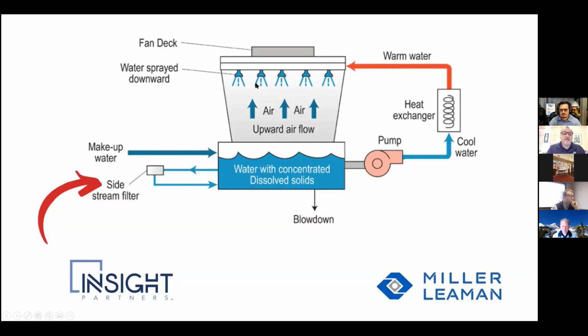We're going to be talking about side stream filtration, where we're pulling it out of the sump at a certain percent. Typically, the way that I design it, to keep it real short and simple, say it's a 1,000-ton cooling tower, it's flowing approximately 3,000 gallons per minute. We typically take 10% of that, which is 300 gallons per minute, and do a side stream. That's also going to hit the numbers for your sweeper system. So, example, on a 1,000-ton cooling tower, the sweeper design from Marley is around 286 gallons per minute at 20 psi. So we're right in that ballpark.